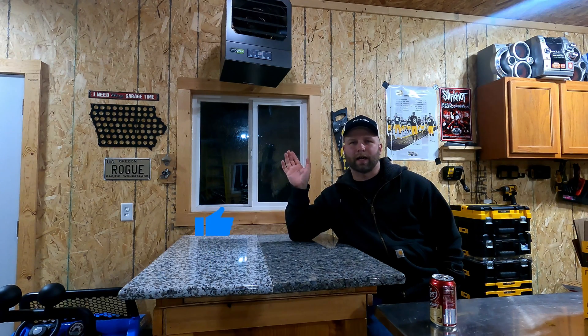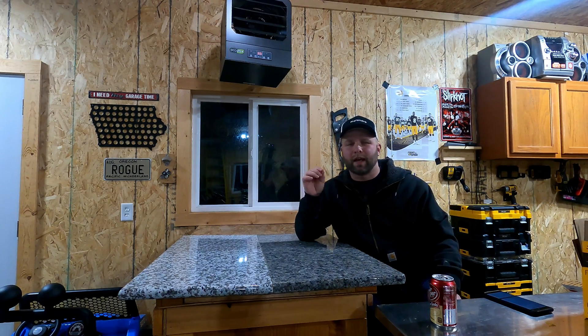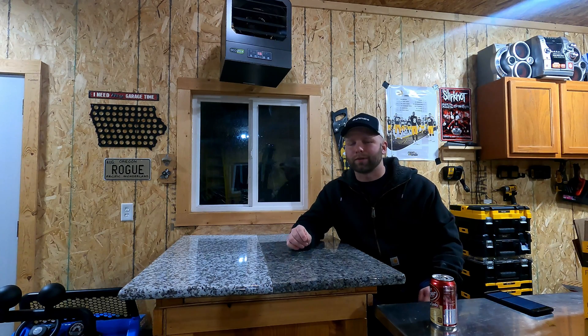This is a 7,500-watt heater with basically a two-stage heat between 7,500 watts and 5,000 watts, which automatically adjusts according to what power is needed to heat the room. Electric may not be quite as instantaneous as you'd expect from a forced induction heater. Some of those smaller gas heaters are typically around 50,000 BTU. This 7,500-watt unit has a max capacity of 25,600 BTU per hour.